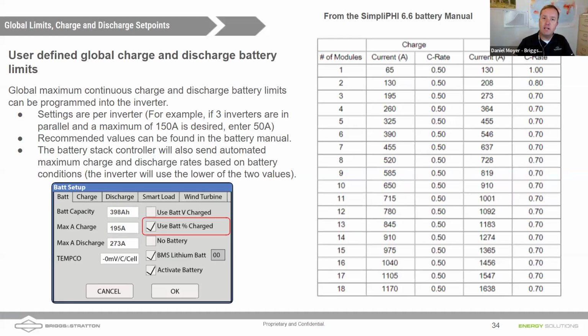But the Sol-Ark 18K can do 18,000 watts from batteries to loads, so I'd say the minimum you need to support it is two stacks of 6.6 batteries. If you only put in a single full stack of three 6.6s—just under 20 kilowatt hours—it can only discharge 14,000 watts, robbing the Sol-Ark 18K of 4,000 watts.